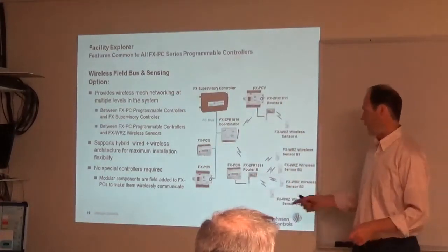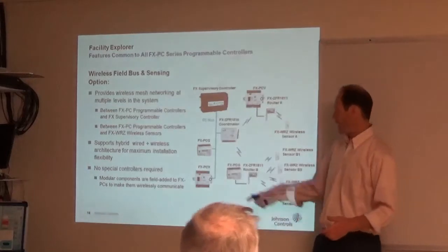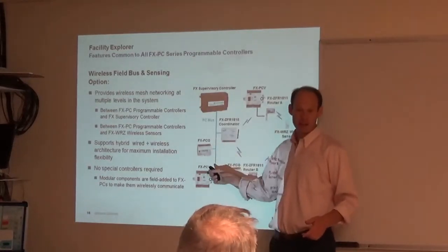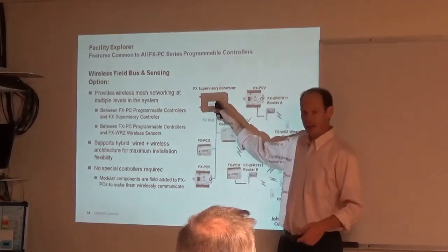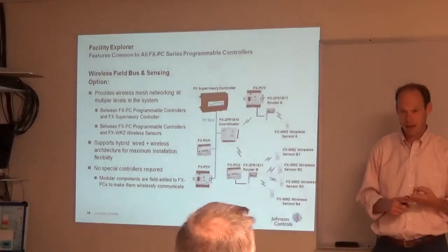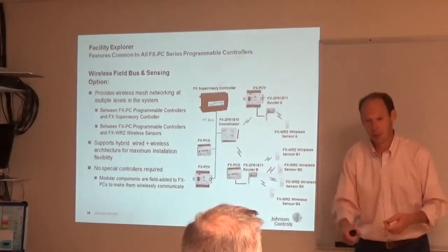part of the software, when you import a controller, and I'll show you that later, I have an application called a CAF file that I downloaded into here that says you are an AHU or you're a rooftop unit or you're a fan coil, whatever the case might be.